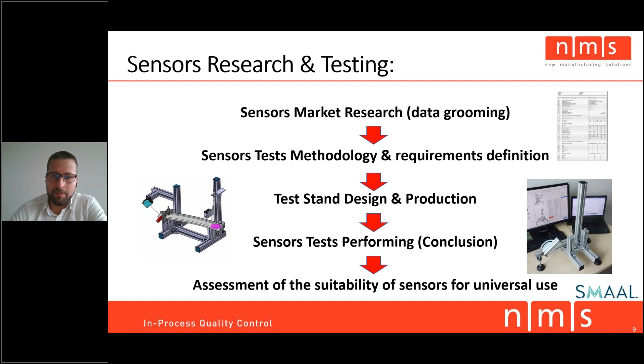Regarding test methodology, we need to have something like stable conditions as the initial one. So we measure all of the sensors at the same time. This is most important because then we are able to secure the same condition for the measurement. And also important is that the temperature is measured continuously during the test, because then we can find some pattern in how the sensors behave with respect to changing temperature.